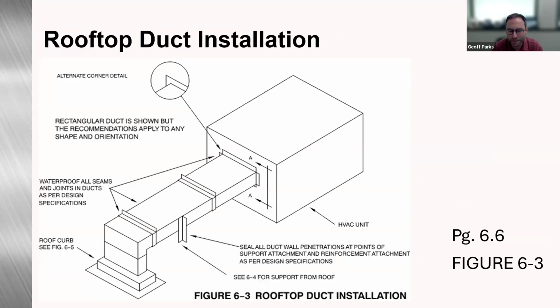Look, here we have figure 6-3, rooftop duct installation. This is just a basic generic detail, a little bit of duct coming off a HVAC unit, and then turning down into your roof curb at your roof penetration. Couple notes here, waterproof all the seams and joints as per the design specifications. The roof curb would be per figure 6-5, which we will take a look at here shortly.